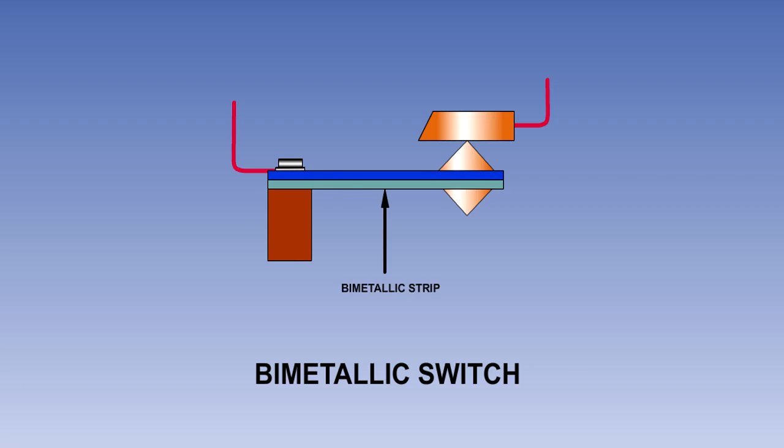The switch consists of a bimetallic strip made up of two strips of dissimilar metals bonded together. The strip is fixed at one end, with the other end free to move up and down. The free end has an electrical contact on it. At normal temperatures, the strip is straight. In our example shown here, when the strip is straight, its contact is touching a fixed contact.